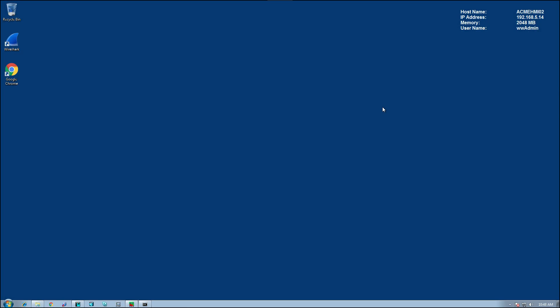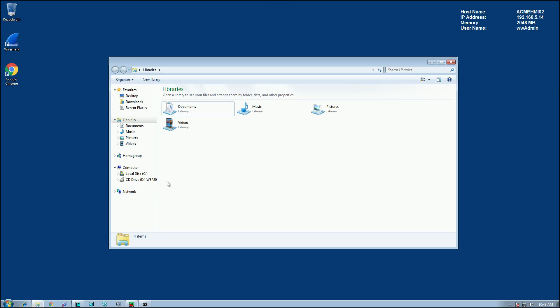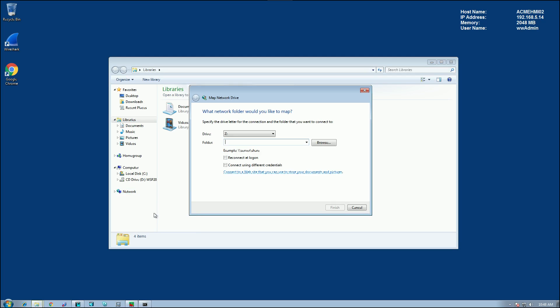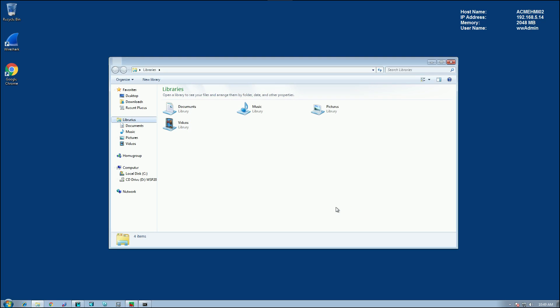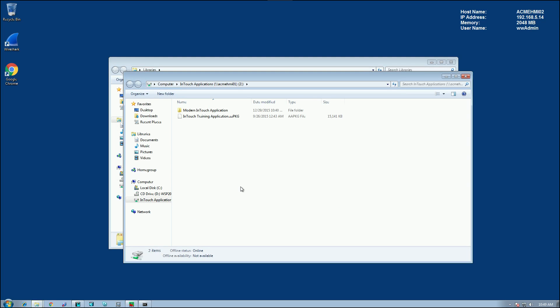On the remote viewing node, the first thing I want to do is open up Windows Explorer, and I'm going to map a network drive to the location where my InTouch application is being stored. It's Acme HMI 01, InTouch application. This is our shared directory. Also, I'm going to select reconnect at logon. That's really important. I'll click finish. And we see that we have our application.